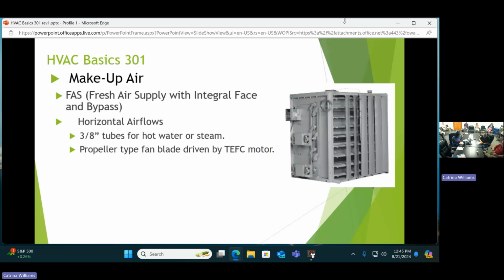These are propeller driven, so you just have an axial fan on the back end driven by a TEFC motor. We've talked about before, axial fans are good because you can move air with less horsepower, but the limit is they can't handle much static. I'll explain that in a little bit more too.